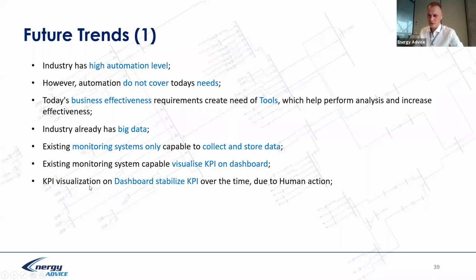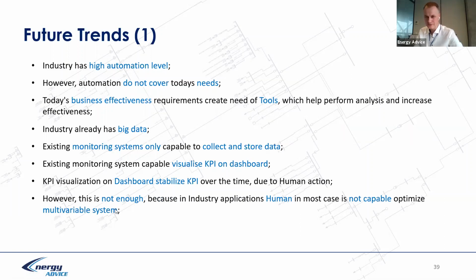KPIs by themselves, visualized on a dashboard, stabilize the KPI. Of course, when we have fluctuation, we can assume and make decisions and impact, and we stabilize the KPI through human action. However, it's not enough to just stabilize KPIs, because when we have an efficiency number, for example boiler 87, is it good or bad? 87% at maximum heat production is probably not very bad, but 87% at minimum operation is not so good.